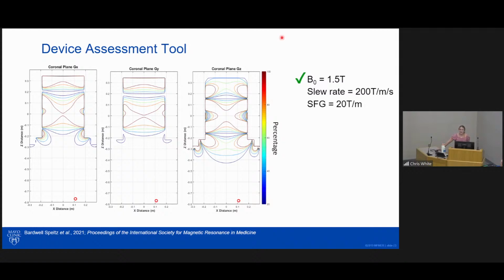I feel like that's a pretty good study because we're able to see, within 5 centimeters, the field strength at the device location. So that is telling us whether or not it is safe to scan the subject. Meeting the device conditions means that you can safely scan the patient. Those mean the same thing. You meet the conditions, you can safely scan the patient. But is it too conservative? Is this too conservative? Yeah.